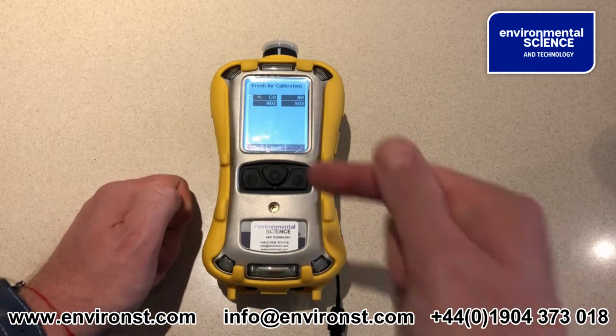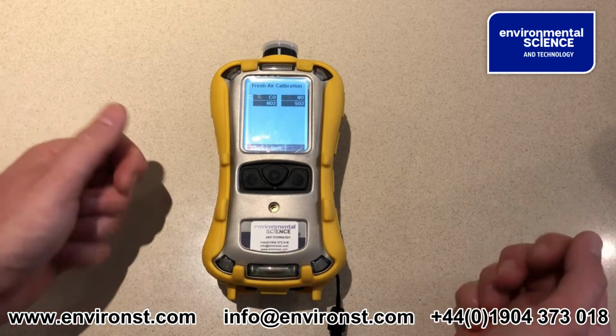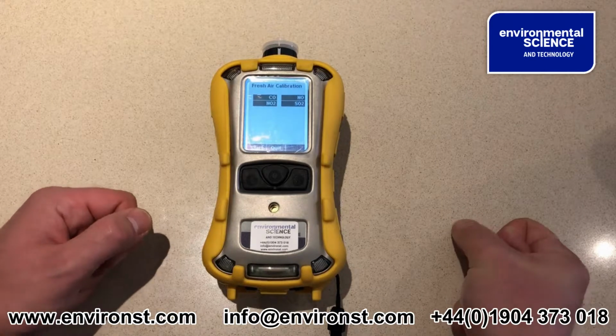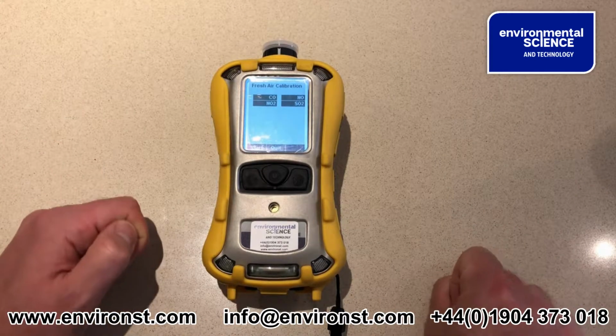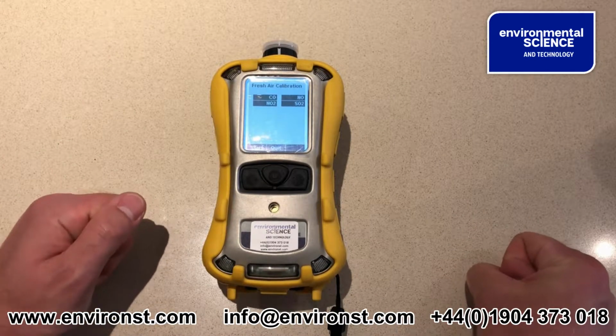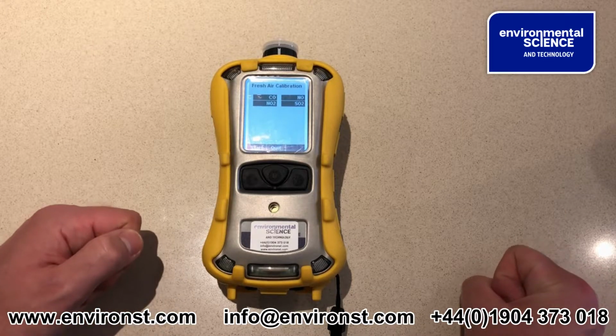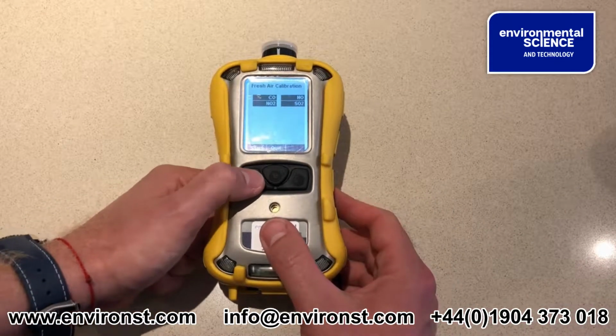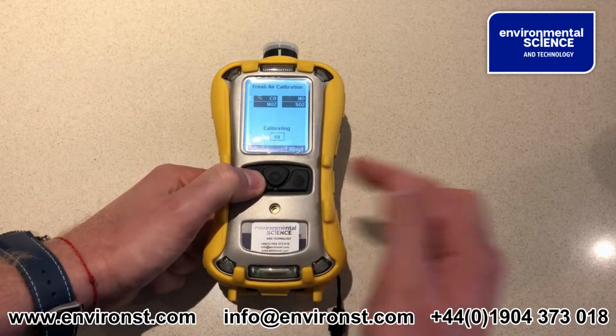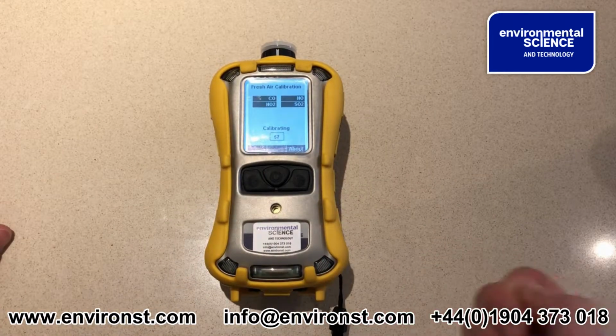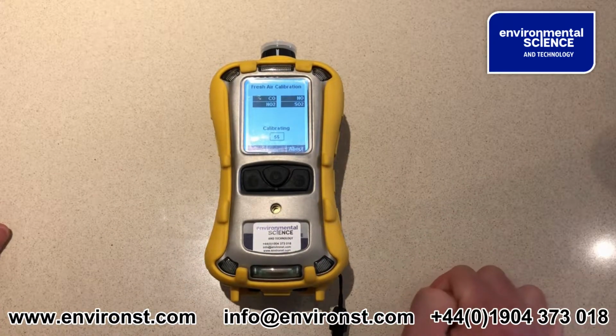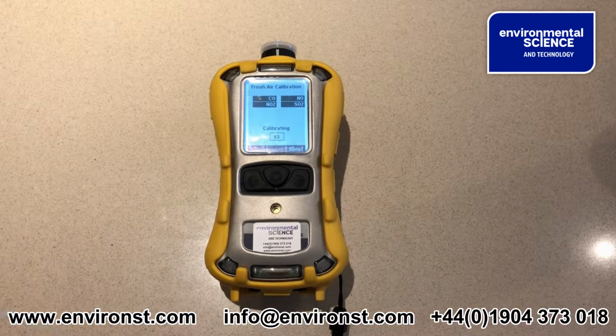You'll notice CO2 isn't on here because we have CO2 constantly at approximately 400 parts per million. If you zeroed it now, you would have an artificial zero, 400 parts per million higher than it should be. So we're going to say start, and it will do a 60-second zero. We'll just fast forward through this because you don't want to be watching a clock ticking down for 60 seconds.